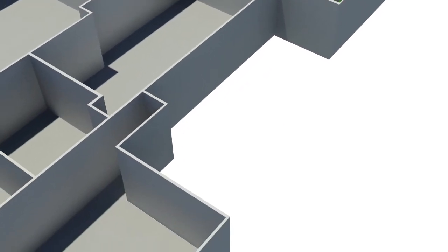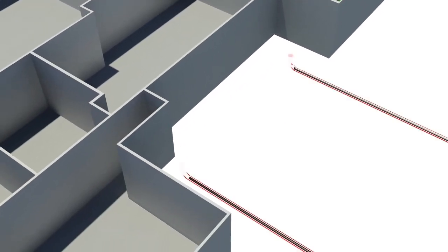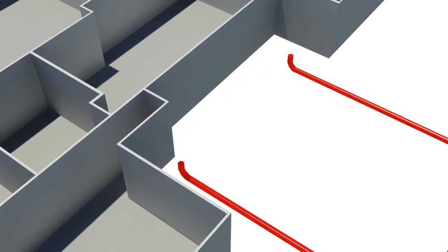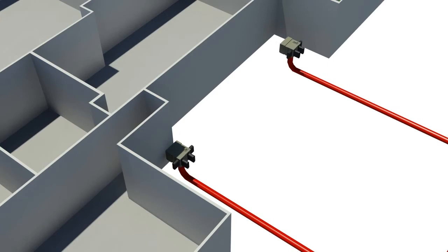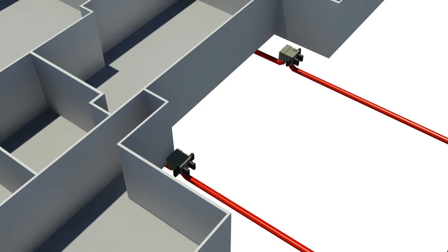Commercial power is delivered to this facility through two separate feeds. This dual power bus configuration is conditioned by six UPS units: four 400 kVA Liebert units and two 150 kVA Liebert units. These units provide a true redundant A and B feed to the raised floor.